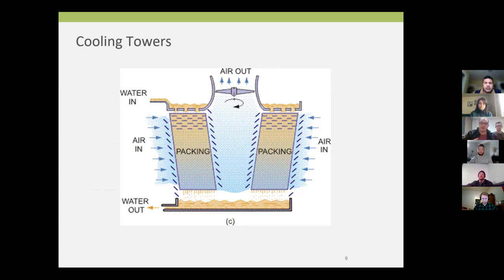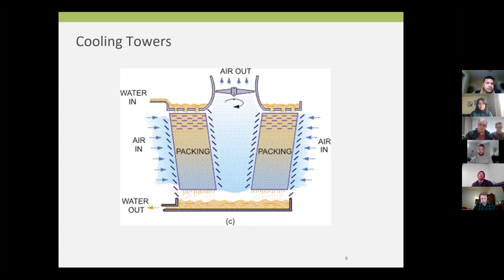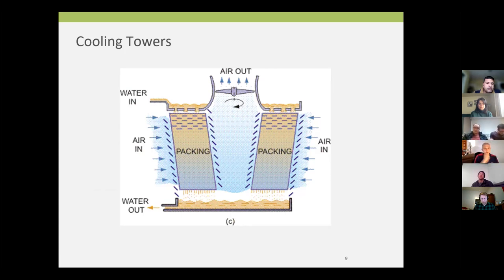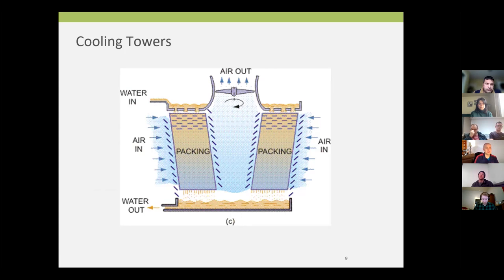Approach is how close this gets to the theoretical. Typically, if you're in that 10-ish range, you're doing really well. Now, that approach of 13 is based off a design condition. So you're going to say, on a 100-degree day in Utah, when the humidity is 40%, can it achieve 13 degrees? You may go out there and find it's 100 degrees, but the humidity is only 15%. So it's going to be less than that. That's why I say if you're around 10, you're in good shape. If you're at 20, there's a problem. If you're at 3, double-check your readings. It's very possible you may be at 3 just based on the ambient conditions. But if you're at 20, your cooling tower offers you an opportunity for energy efficiency.